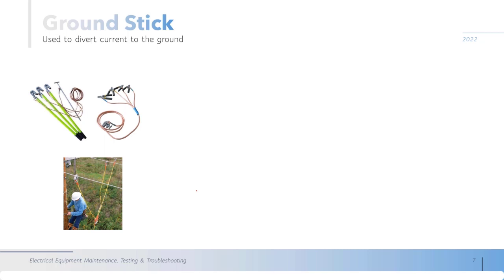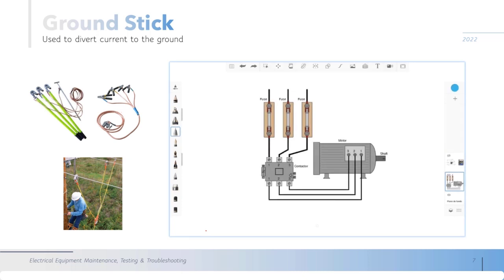So let's see an example of how we use this ground in motors. Let's suppose you have to work in this motor here and the motor is running. That means the voltage from this power supply with fuses going through this contactor. The contactor is now closed, meaning this line is in contact with this one, this one is in contact with this one, and this one with this. So the motor is in voltage and it is running.